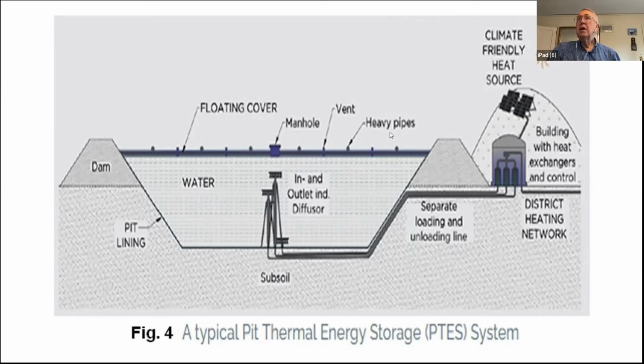And then they have a very large array of solar thermal collectors, so that all summer long they're collecting heat from the sun, putting that heat into the water pit. And the array of collectors is so large that they can get close to the boiling point of water, believe it or not. So at the end of the summer, they have temperature near the top of this water pit that's close to 200 degrees Fahrenheit. So they've got to insulate that so that heat doesn't escape. So that's the purpose of the floating insulated cover at the top. That's a very critical design part of this.